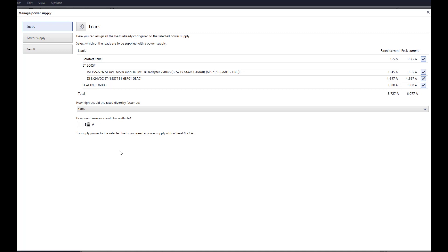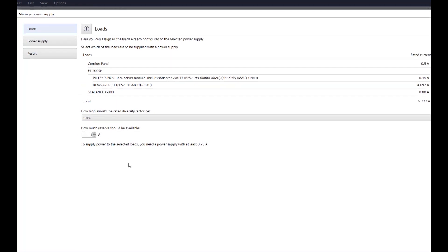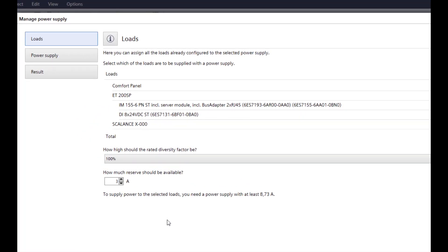In principle, a reserve of approximately 30% of the total load is assumed. In this case, a reserve of 3A is selected. The minimum output current the power supply must provide is already displayed here.